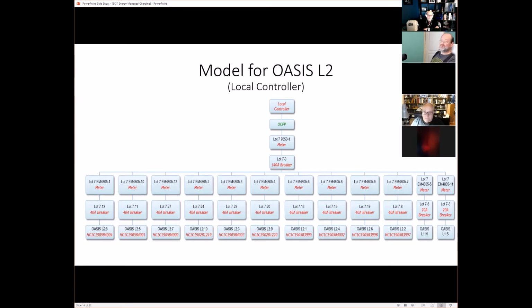At the bottom, we have all the charging stations, where it's labeled Oasis L2:8, L2:5. So these are all the charging stations. It shows that level 2, number 8 is connected to a breaker that's 40 amps, and we have the label for the breaker. It's in slot number 12 in that panel, and above that is an electrical meter. We measure that, and then all of these meters report up to what we're calling lot 7-0, which is the main breaker for that electrical panel, and it's a 140 amp breaker.